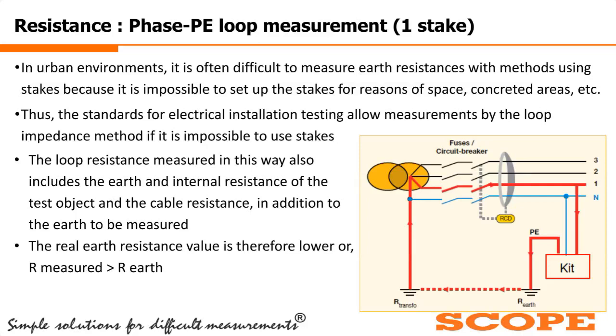So in this method, generally we will use the earth and internal resistance of the test object and the cable resistance, and for that we will use an RCD clamp for the measurement. Generally this method gives an R measured value which is greater than the exact earth resistance, because the earthing of that existing system may come into the picture. So this is the limitation of this method.